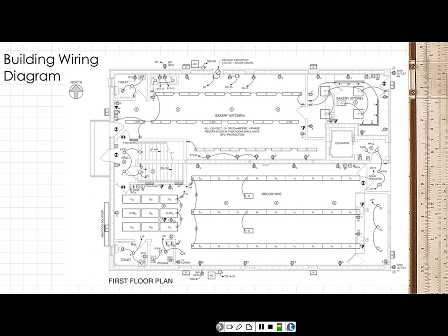So you'll see on electrical prints, they show these wires. They don't show it going back to the panel box. All they do is say, this is what circuit this hooks up to. This means this goes back to the panel box, that arrow right there. This indicates how many wires are inside the raceway that you're going to run over to the panel box. But they don't show you how to get to the panel box. They just show you where it goes. So see, I know a little bit about electrical prints already.